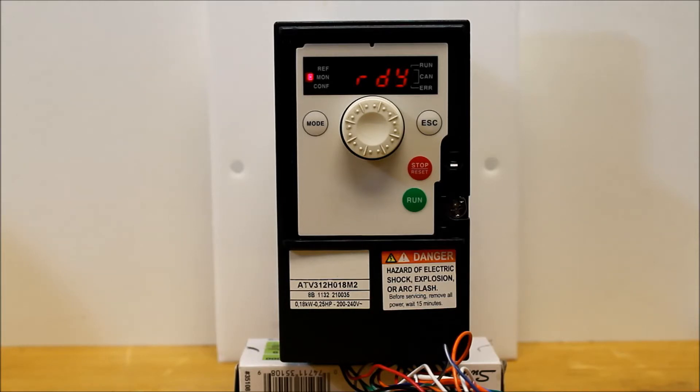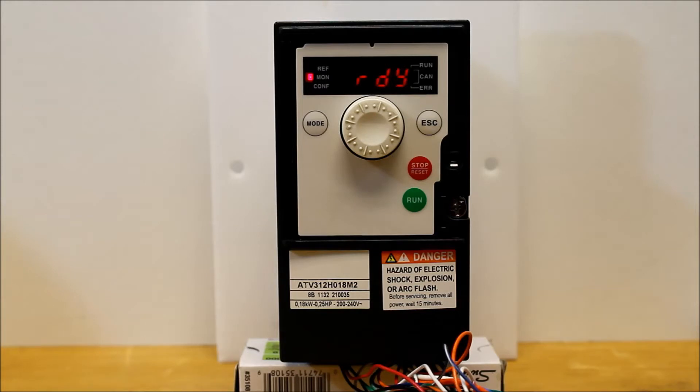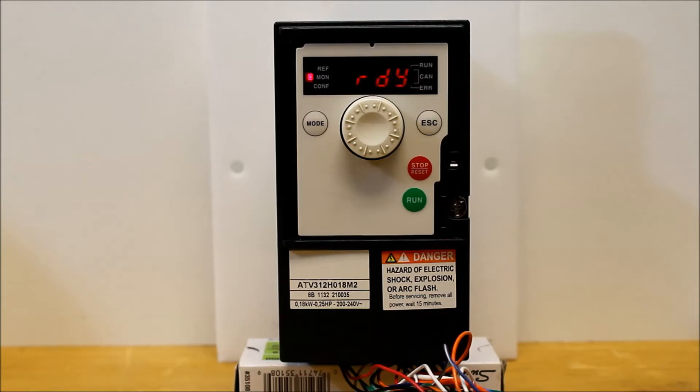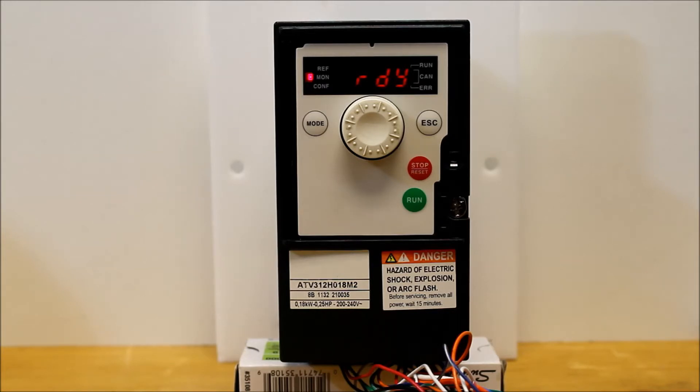In two-wire control, what that basically means is you're allowing the closure of a contact between the 24 supply and the logic input 1 terminal. You can have a normally open contact between it, and when the contact is closed, it will run the drive, and when it's open, it will stop the drive. That's what two-wire means.